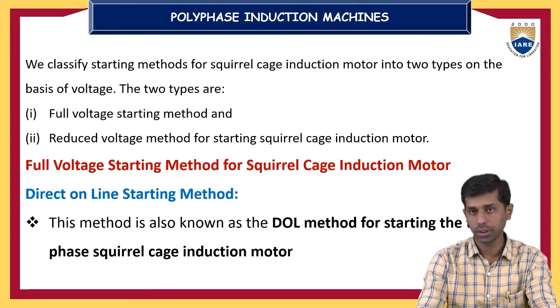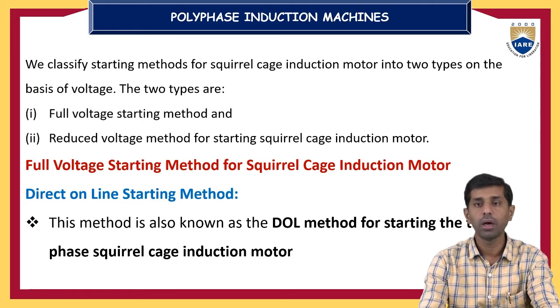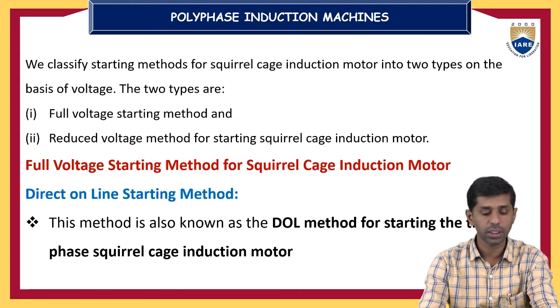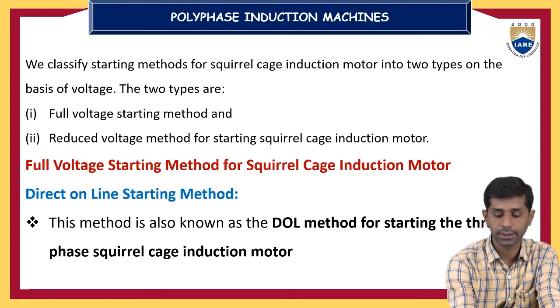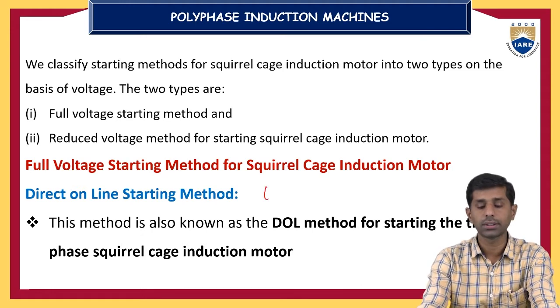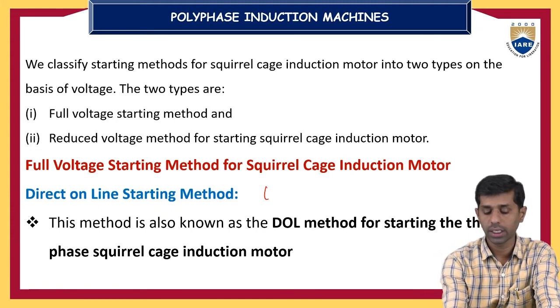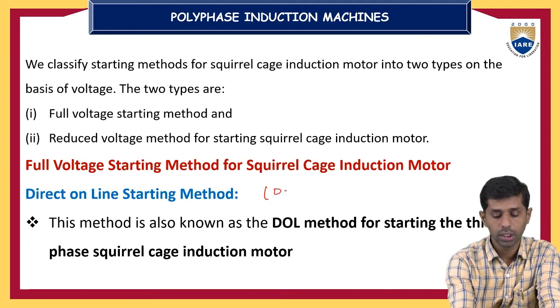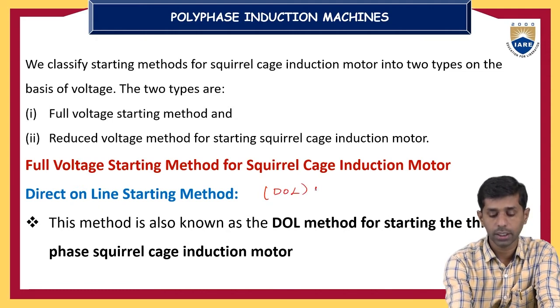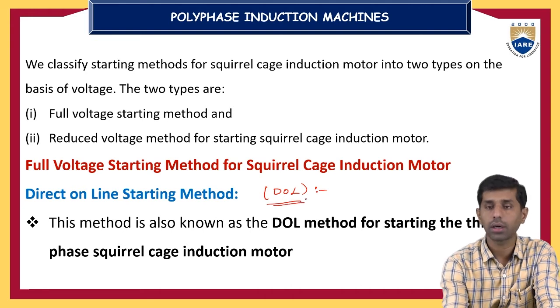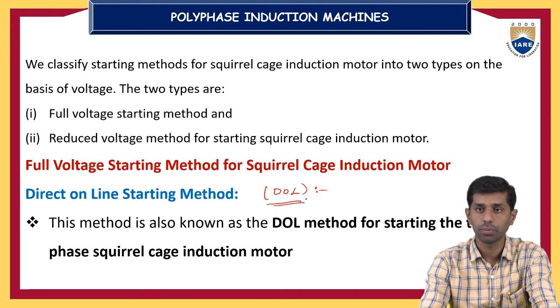Full voltage starting method and reduced voltage starting method for a squirrel cage induction motor. Under the full voltage starting method for a squirrel cage induction motor, one of the starting methods is called the direct online starting method, also called the DOL starter, for starting the squirrel cage induction motor.